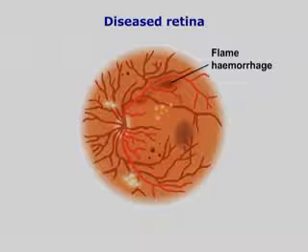There is also a green light, or, as it should be referred to, a red-free filter. It enhances blood vessels and hemorrhages and helps to differentiate black pigmentation from hemorrhages. There is also a grid which is used for mapping out the position of any lesion. A slit-like beam is sometimes used to assess elevations or concavities on the retina. The strength of the beam can be adjusted with a rheostat control on the handle.